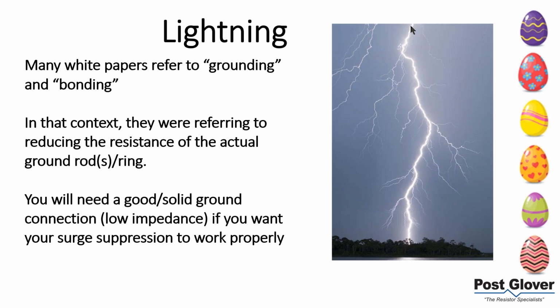In the reading that I found, they basically refer to grounding and bonding. Typically in my experience, what they're referring to is the actual resistance of the ground connection you have to earth, and your ability to get a good low-resistance ground for your ground rod and your ground ring. There are a lot of papers about that. They talk about bonding, equipment ground, et cetera. It's not really the same thing as system ground.